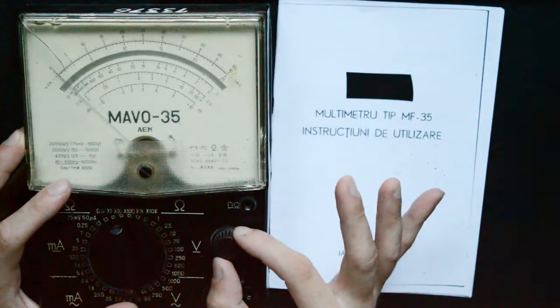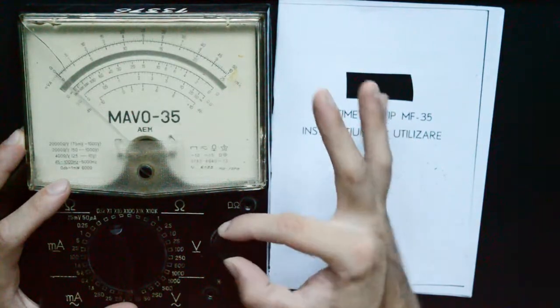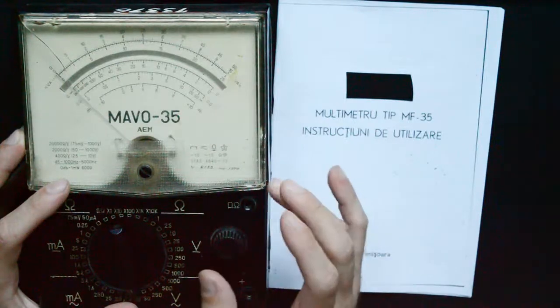But there is still a secondary knob used for tuning the ohmmeter. Depending on how full the battery is, this will be used to calibrate the full scale. Okay, finally, let's look at the back.